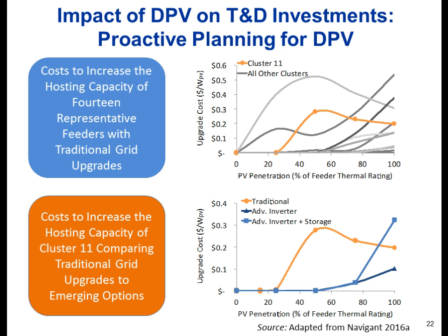The availability of advanced inverters capable of supporting voltage through power factor controls can increase the hosting capacity and also lower the upgrade costs. The study authors note, however, that taking advantage of this advanced inverter control requires system-wide telecommunications and distribution management systems that are neither currently available at Dominion nor included in these upgrade cost estimates.